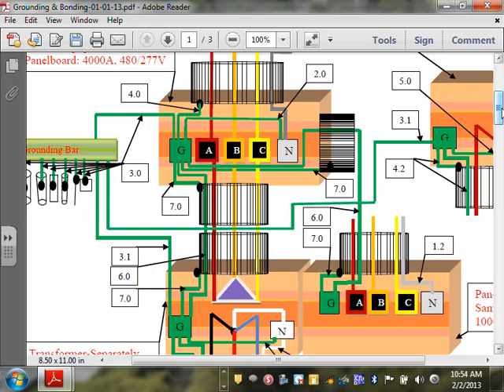Daisy chain them with the 2 AWG, or the same size, 2 AWG, 2 home runs, 1 from every conduit into the ground bar. So I can take 1 from every conduit to the ground bar, or if I have 4 of them on this, and typically from the bottom, coming 1, 2, 3, 4 here, 1, 2, 3, 4, or daisy chain them 1, 2, 3, 4, all the way. Either way, the size is still 2 AWG. Doesn't change. Any comments, any questions, guys?